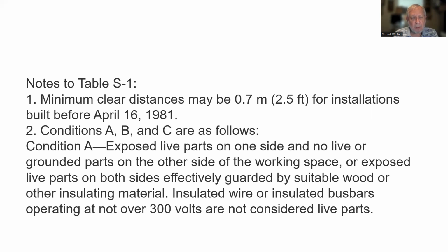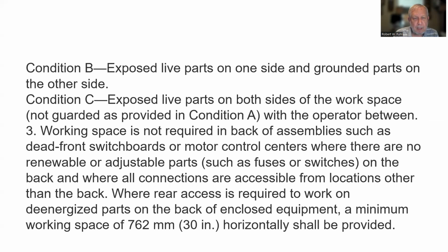Conditions A, B, and C are as follows. Condition A, exposed live parts on one side and no live or grounded parts on the other side of the working space, or exposed live parts on both sides effectively guarded by suitable wood or other insulating material. Insulated wire or insulated bus bars operating at not over 300 volts are not considered live parts. It says insulated, okay.